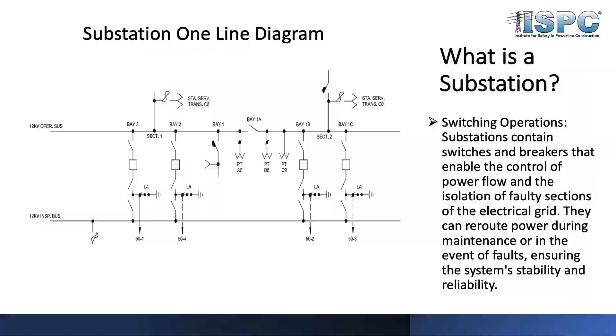so we can not only reroute power within the substation, but we also have field ties and things that we can do out in the distribution network to be able to reroute power and keep the lights on for everybody while we fix faulty equipment. We also have the ability inside the sub, we need to proactively maintain this equipment, so we have the ability to reroute power within the substation and take equipment out of service so that we can maintain it. All the while, nobody ever knows the difference that we're even doing anything. The lights stay on. We can do that through switching operations inside the substation here. Okay.